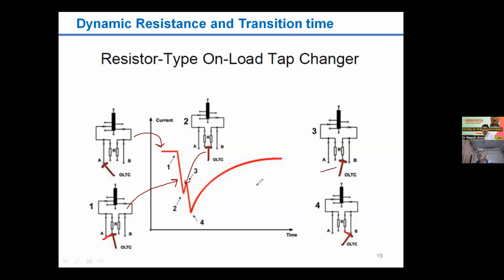And then the next position is 3, where again the drop in the current will be seen, because the drop in current is taking place due to the resistance coming into the picture during the transition of the tap from one position to the other. So when it reaches position 3, from 1 to 3, the current drop was taking place. But in between, when the two R's were in parallel, a slight increase has taken place.